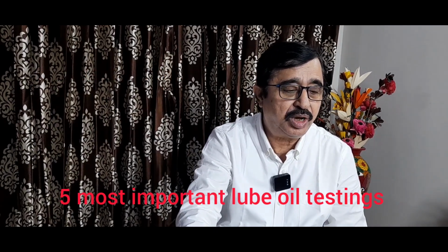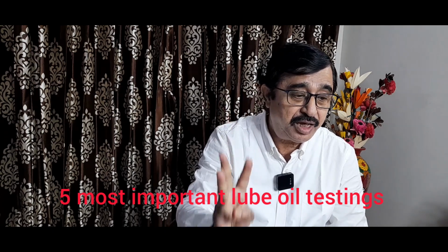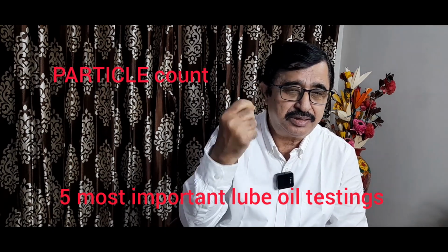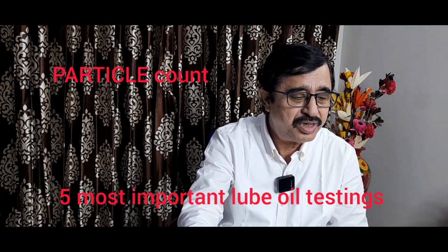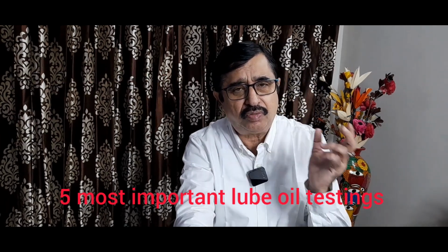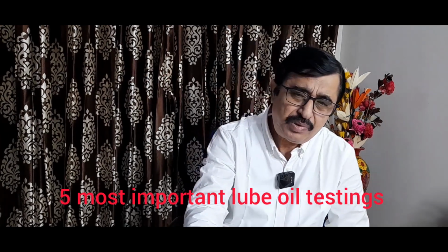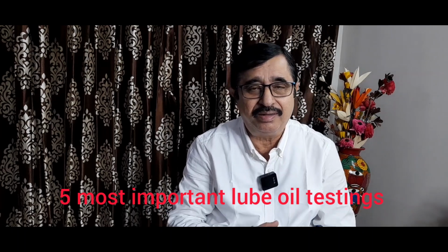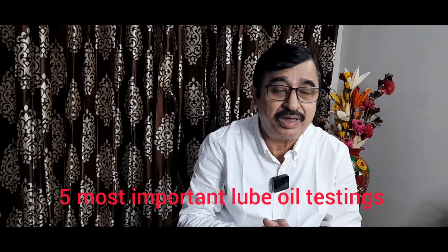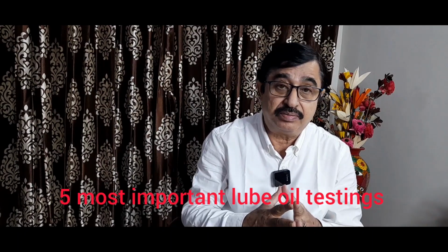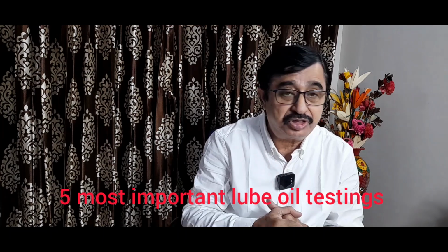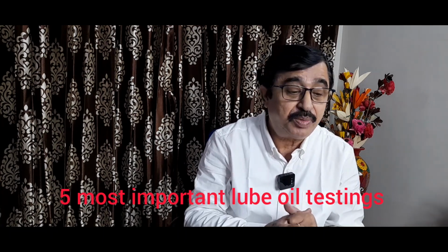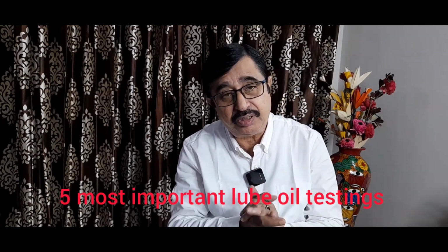Now we go to number 3. Number 3 important is the particle count analysis. This is very important because we have seen that studies carried out all over the world showed a result that 70% of the equipment failures in the circulation system or the lube oil system are caused by particulate contamination in the lube oil.